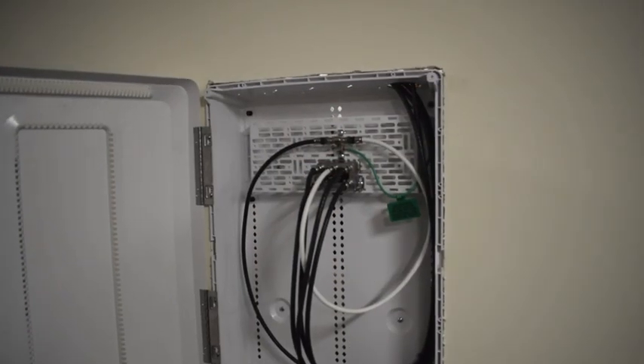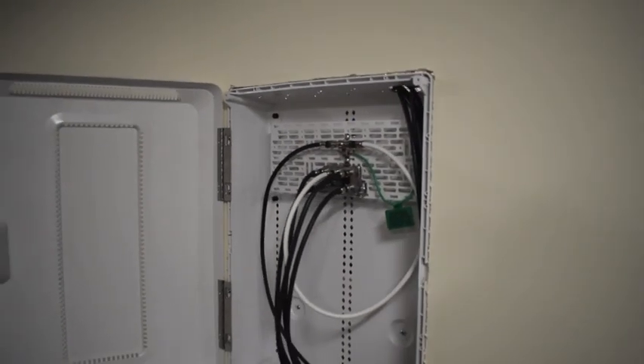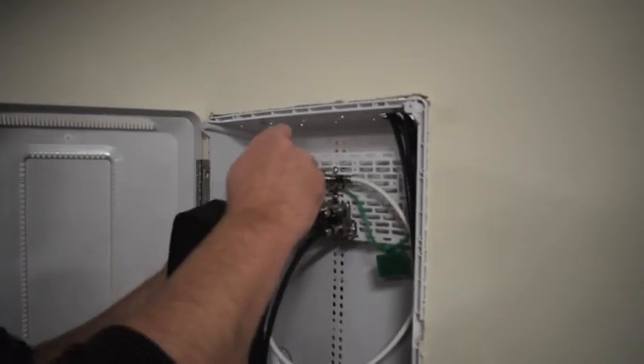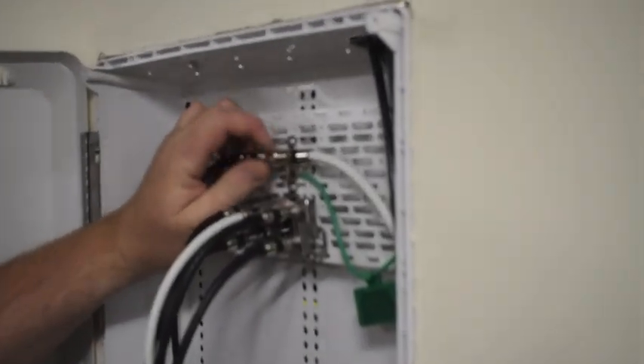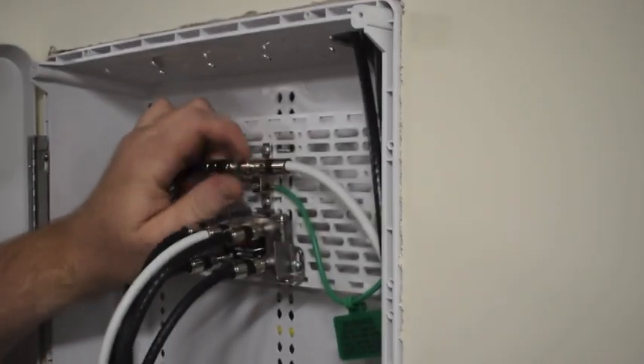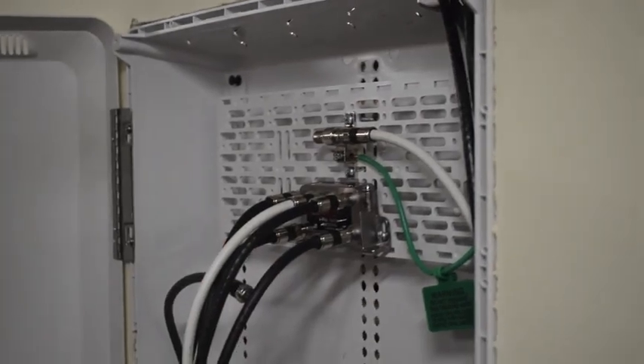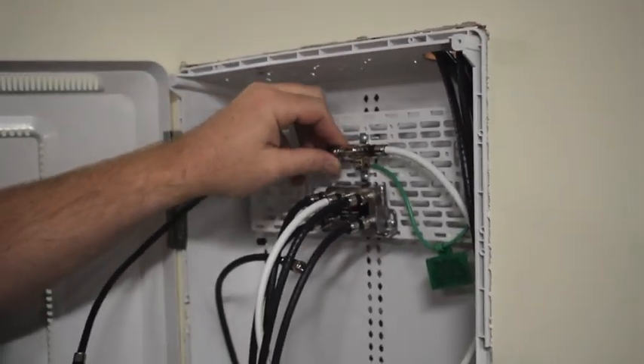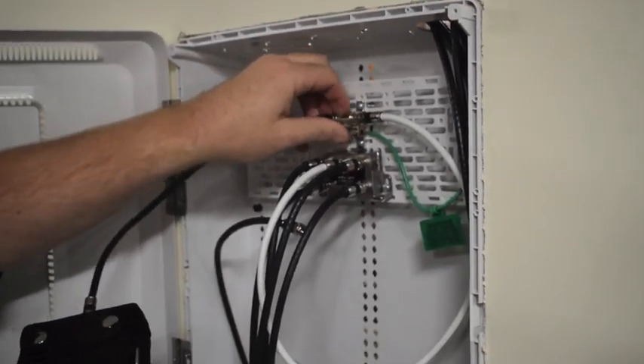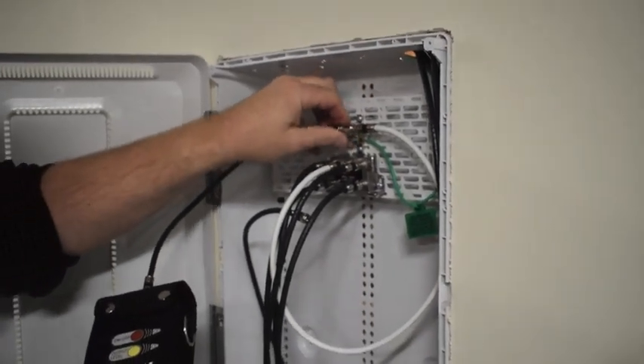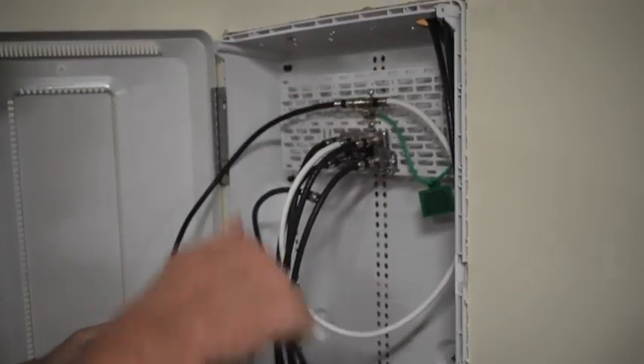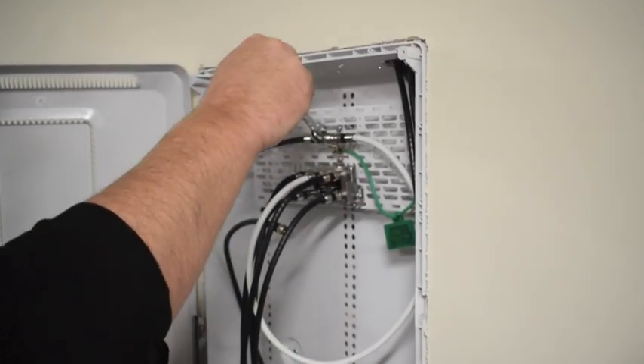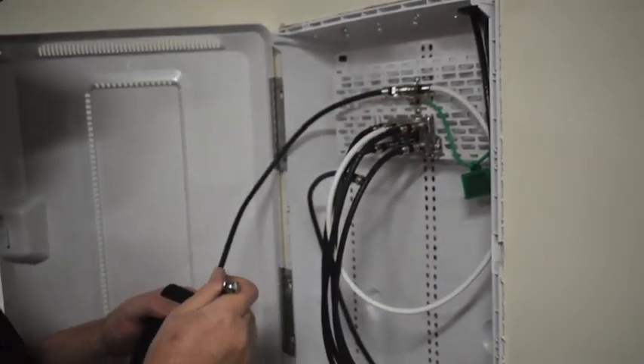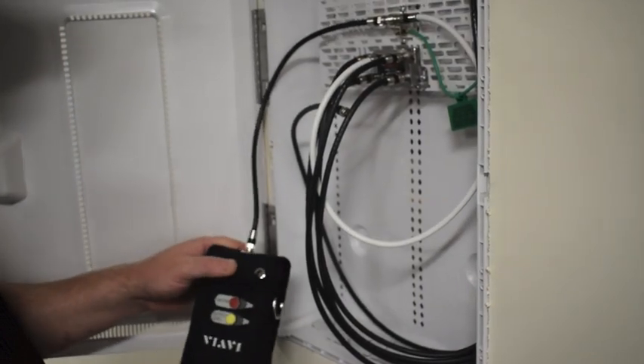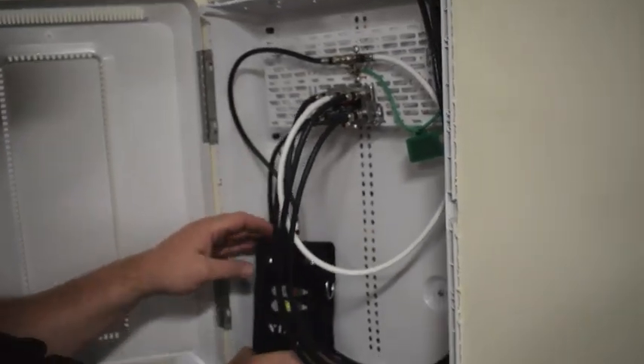The first step in pressure testing is to disconnect the input of the ground block. You're going to connect the transmitter to the input side of the ground block where you just disconnected the service drop. Ensure that that connection is wrench tight. Also wrench tight on the top of the transmitter. This will prevent any inadvertent leakage in this general area.